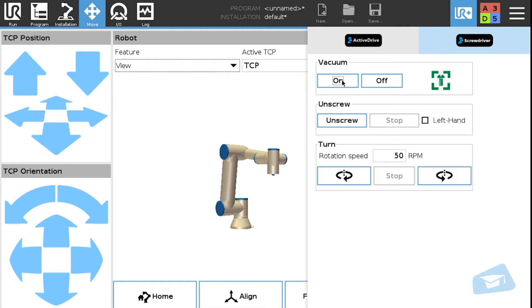If the robot can detect the screw consistently several times in a row, this means the vacuum sleeve has been properly adjusted. If not, adjust the coupler accordingly.